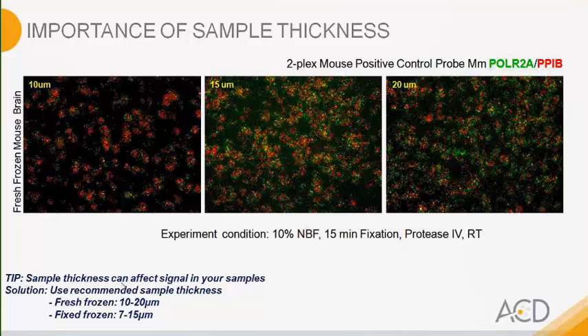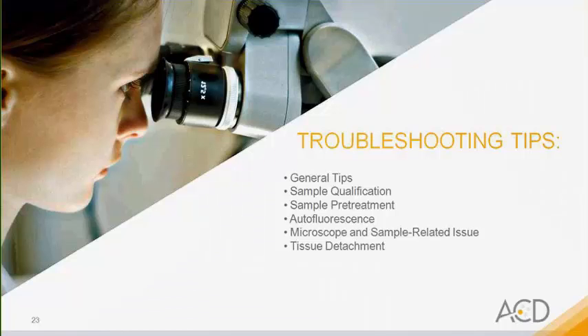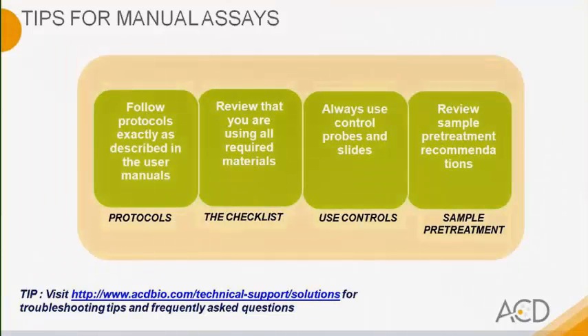So our recommended sample thickness for fresh frozen is 10 to 20 micron, and for fixed frozen is 7 to 15 micron. Moving on to troubleshooting tips. From a very broad, high level, the general tip for the RNAscope manual assay is to always follow protocols exactly as described in the user manual. And also, please review the checklist. Make sure that you are using all the required materials. And also, always use control probes and slides to qualify your samples.